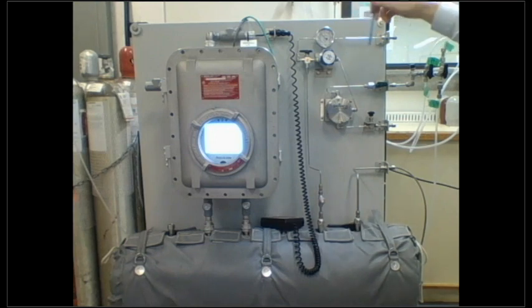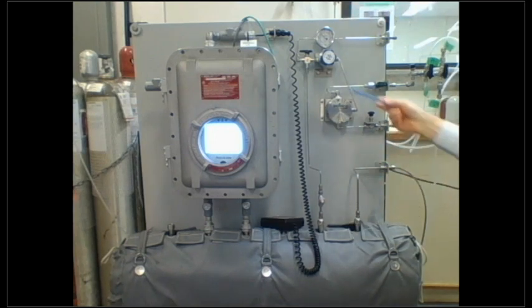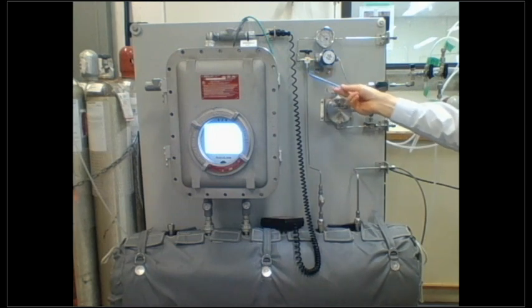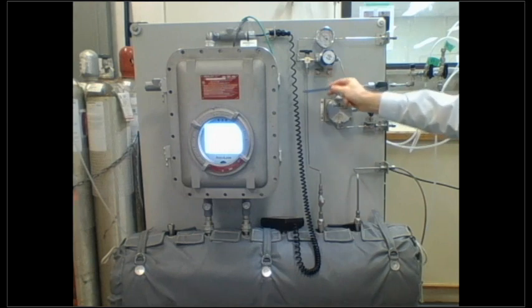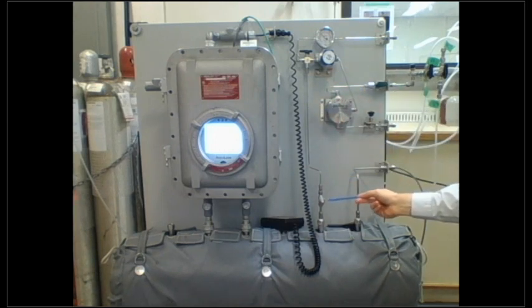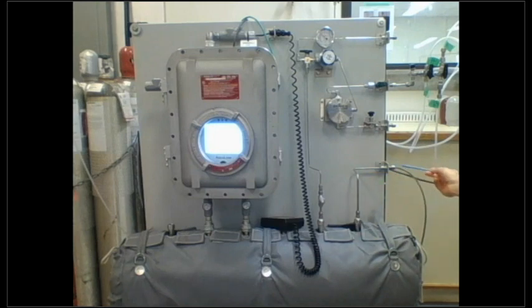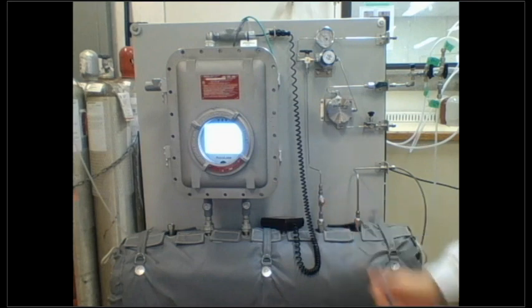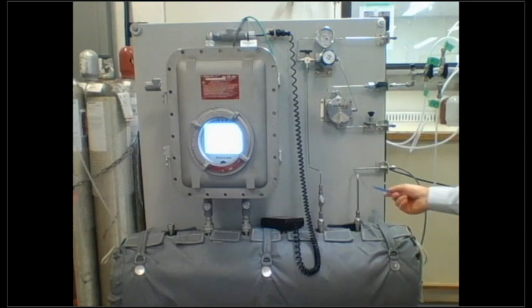Gas then flows into the cell. This is a metering valve here. And then here's the vent that the gas exits the cell to. So this metering valve is used to balance the pressure in the cell as well as the flow. That flow is typically between 2 and 3 liters a minute, and it exits out of the vent line here. Typically, you would vent that either to atmosphere, or you could also send it out to a low pressure flare. We can pump against on the order of 2 or 3 psi. So if you do have a low pressure flare on site, we can pump the effluent from the cell into that.